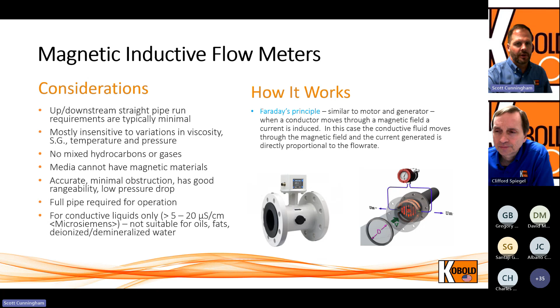So at this point, we've covered high level ultrasonic, and we've covered mag meters, and we've put together this kind of compare and contrast, right? What are the advantages? Why would you use one over the other? And we get asked this all the time. So really, when you look at ultrasonics, if it's a non-conductive media, but you're looking for all the advantages of no moving parts and these newer technologies that are repeatable over time, it's a great choice.